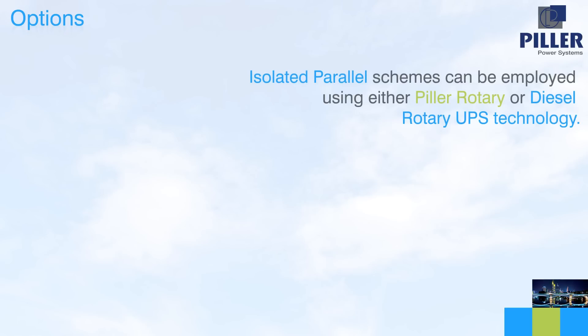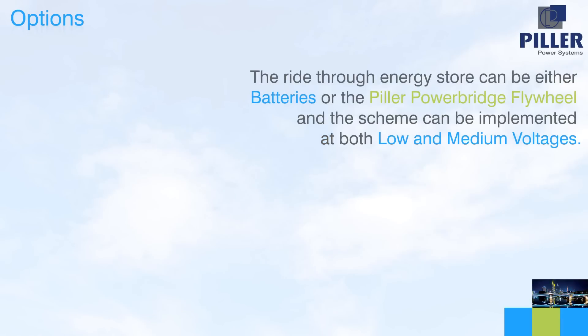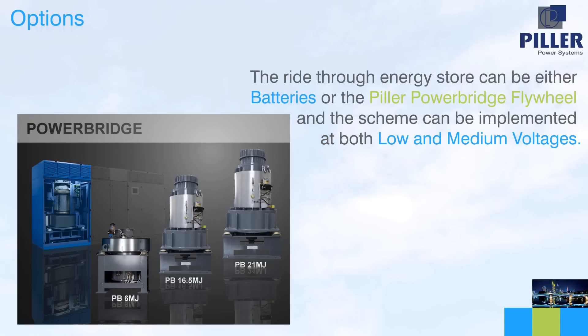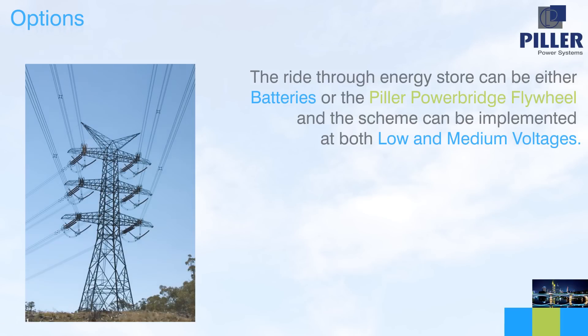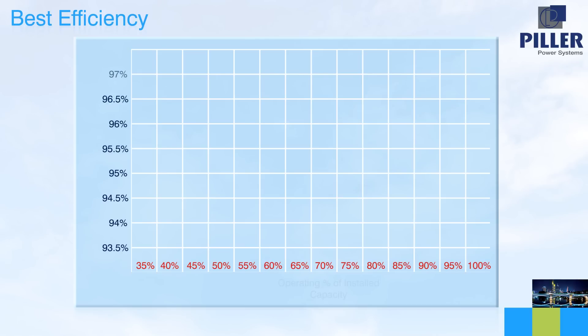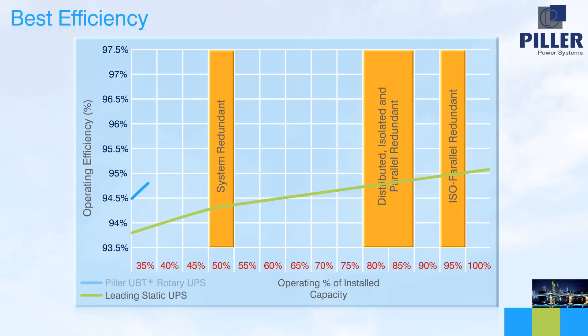Isolated parallel schemes can be employed using either Piller Rotary or diesel rotary UPS technology. The ride-through energy store can be either batteries or the Piller Powerbridge Flywheel, and the scheme can be implemented at both low and medium voltages. The isolated parallel concept is the only solution that can offer a highly reliable, fault-tolerant, and concurrently maintainable system at the same time as delivering the highest electrical efficiency. This difference in efficiency, particularly at partial loads, brings about significant economic benefits for the data center user.